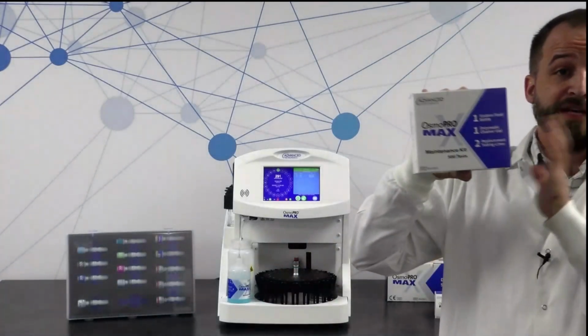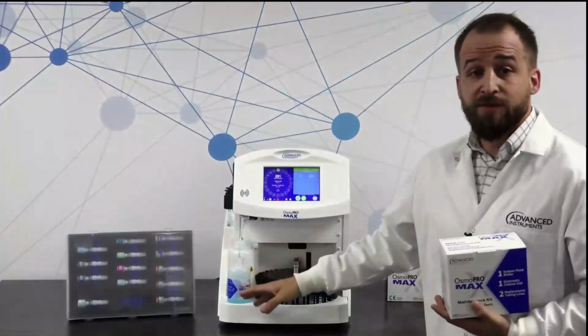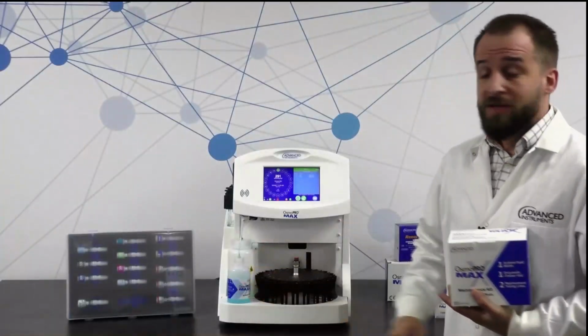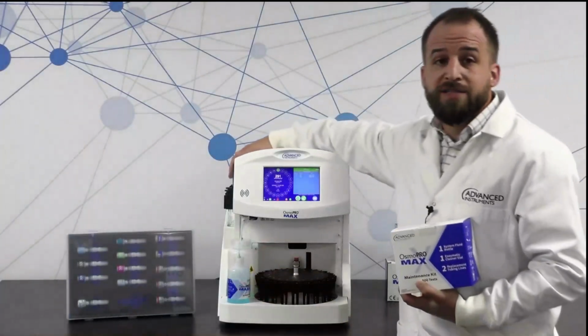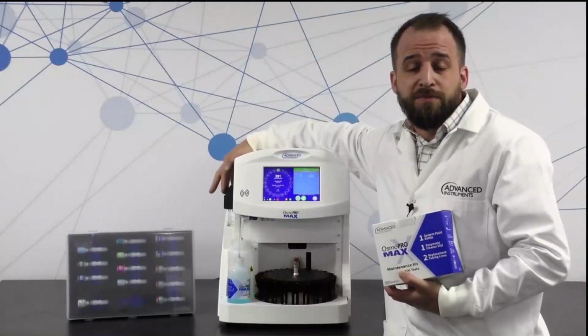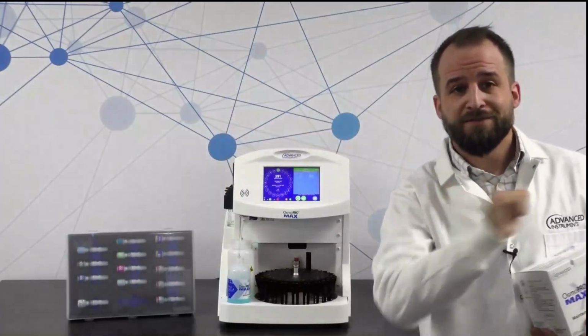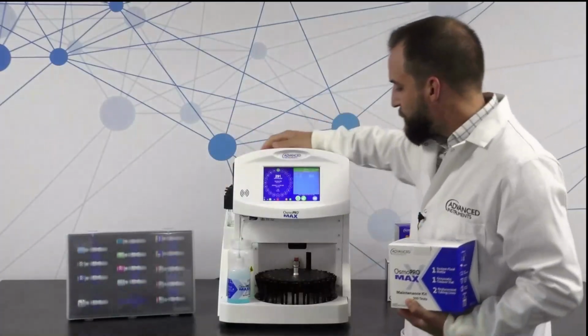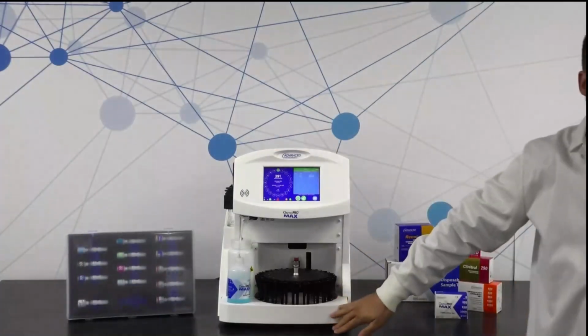When you hit 500 tests, you just have to change out the system fluid, which is the blue stuff over here. You have to change out the peristaltic tubing lines, which are really easy—they're under these black covers over here. It's righty-tighty, lefty-loosey, as we say here in the States. And then run an enzymatic cleaner through the system.